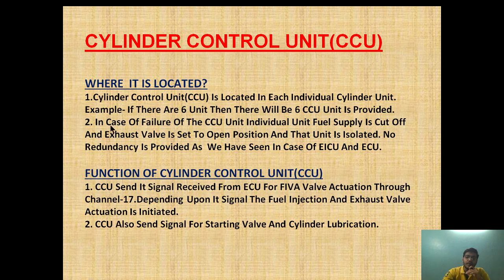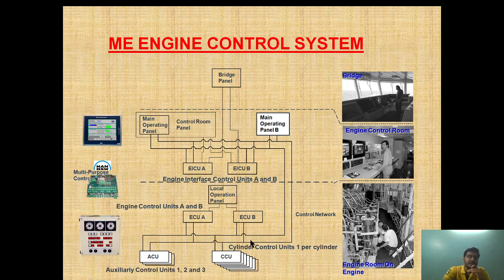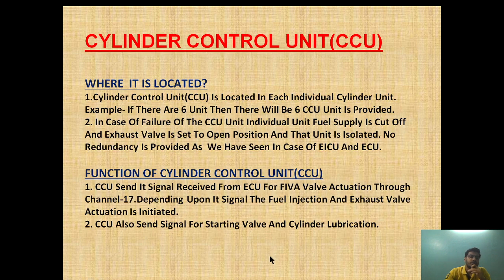The next question is whether there is a backup for CCU like ECU A and ECU B, where if one fails the other comes online. The answer is no. In case of a CCU failure, the individual unit fuel supply is cut off, the exhaust valve is set to open position, and that unit is isolated. No redundancy is provided, unlike EICU and ECU.